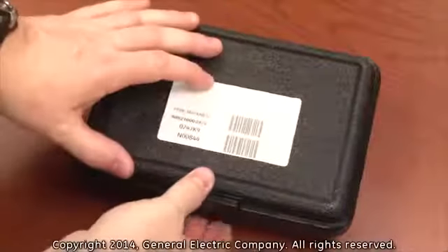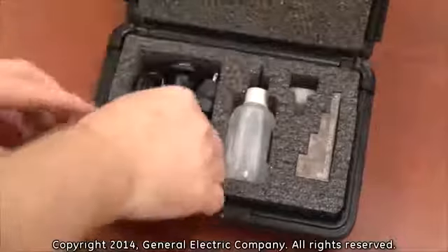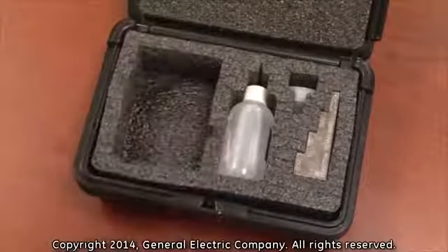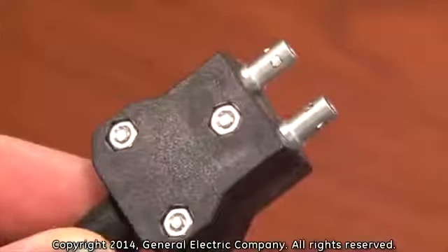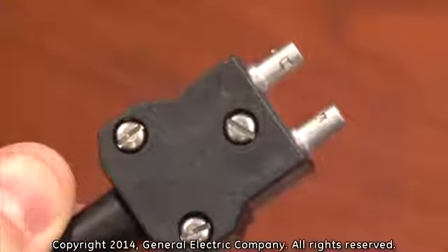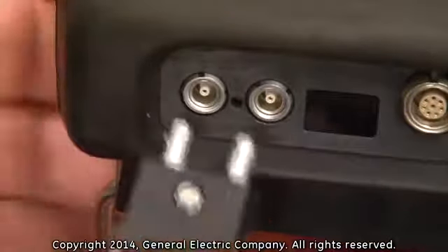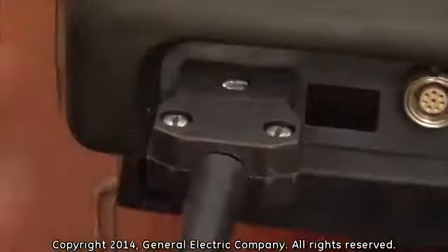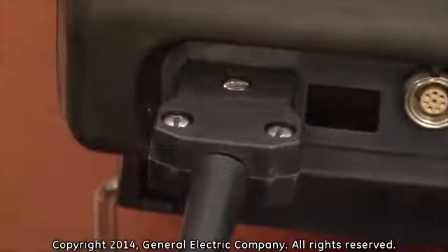To use and calibrate the thickness gauge for measuring thickness of a pipe wall, first connect it to the PT878. The orientation of the thickness gauge connectors does not matter. Gently press the thickness gauge connectors into the transducer connection ports on the PT878.